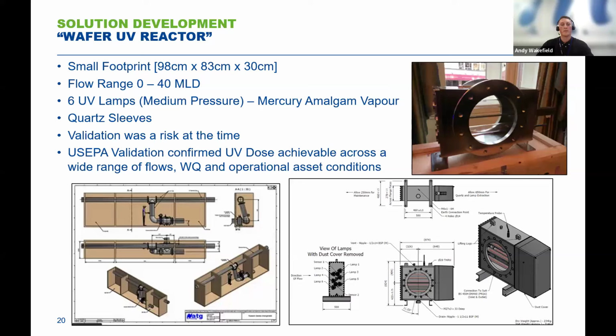They contain 6 UV lamps of medium pressure and contain a mercury amalgam vapor. The 6 UV lamps would be contained within quartz sleeves, and they provided several benefits in that there was physical protection to the lamps. It would protect against fouling, and those quartz sleeves could be replaced as part of servicing. And it also reduced the risk of nitrate to nitrite formation, which is a disinfection byproduct consideration around UV. The proposal would also allow us to install UV upstream of chlorination, mitigating the risk around disinfection byproducts associated with having chlorine within the water at the time of UV application.